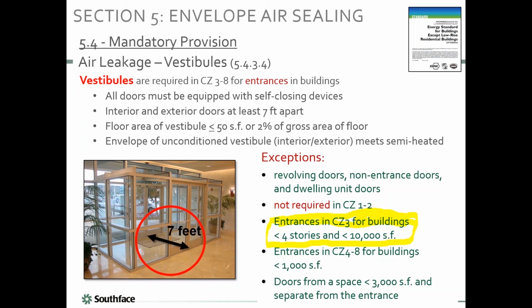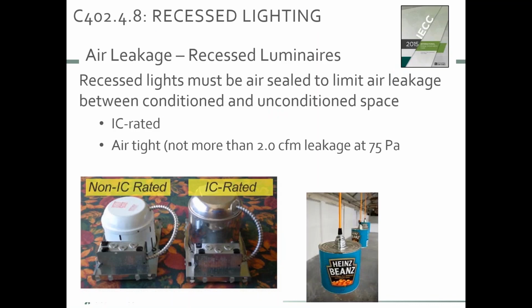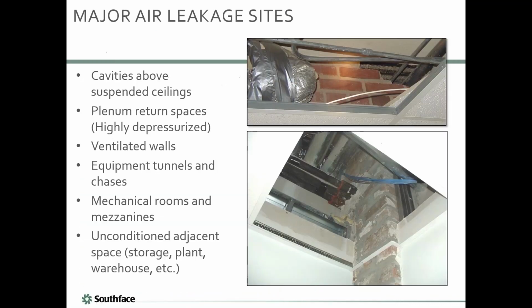So vestibules are becoming much more popular and common in the code. That's just how it rolls. Again, we don't recommend you condition a vestibule. This one was super cooled. It was sweating on the outside. And can lights, we talked about that a little bit.